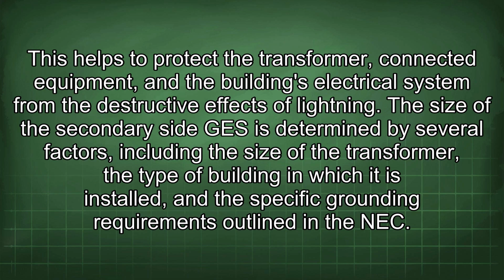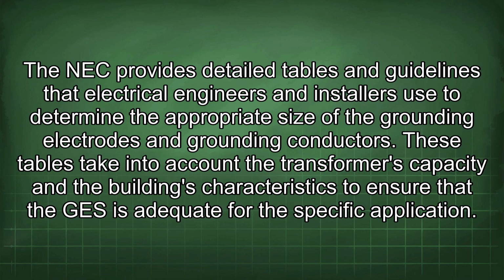The size of the secondary side GES is determined by several factors, including the size of the transformer, the type of building in which it is installed, and the specific grounding requirements outlined in the NEC. The NEC provides detailed tables and guidelines that electrical engineers and installers use to determine the appropriate size of the grounding electrodes and grounding conductors.